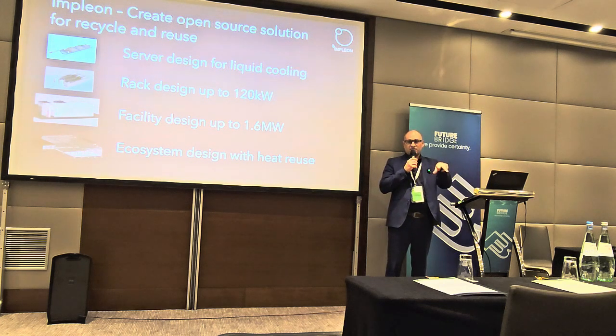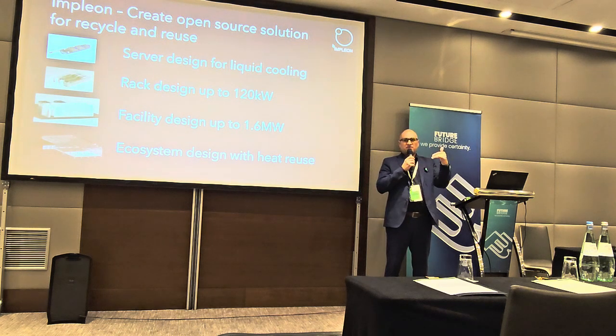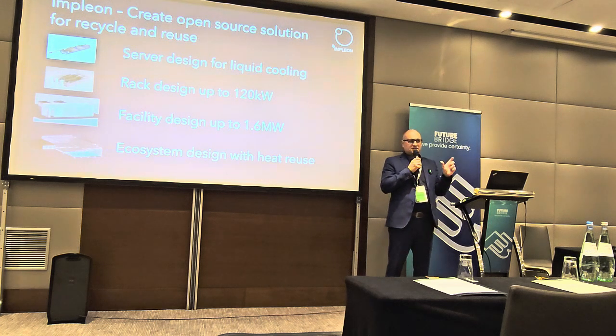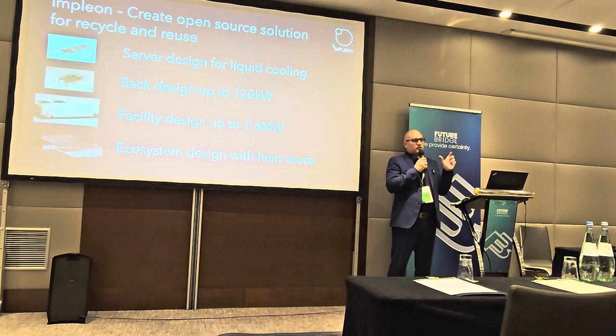Depending on that, you choose the cooling system. But also, if you want to do heat reuse, you should understand what temperature you need to achieve: is it 70 degrees, is it 30 degrees? This also impacts the facility design. This is why it's important to think big.